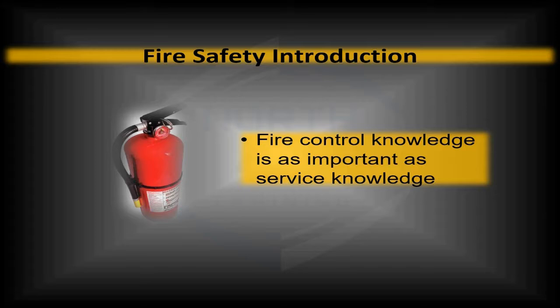Do it at a safety meeting, at an internal meeting at the shop — somewhere along the line. Make sure that you get your hands on a fire extinguisher and you're able to practice. They do have a lot of pushback, so that may be one of those things you're just not prepared to deal with. If the first time you pull that pin is when property damage is at stake, you may be surprised at how much kickback it has. If it freaks you out, you might drop it or hold the handle down in a fashion that's not even on the fire. You only get roughly a minute on most of these fire extinguishers once depressed for your fire suppression.